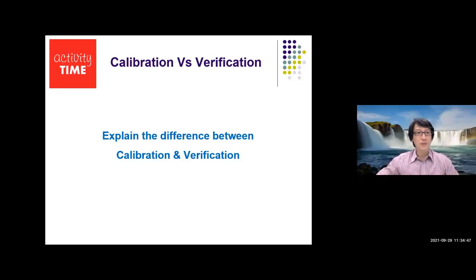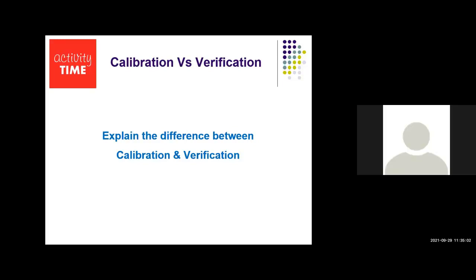Great. Now, in this case, do you calibrate the torque meter, or do you calibrate the torque driver, or do you need to calibrate both? Both we need to calibrate. But for the daily calibration, we need to ensure the torque driver is in good condition.